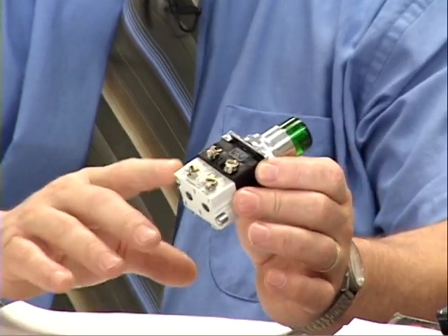And I think, Dan, you were saying that these switches might have normally closed contact symbols shown on them. What were you saying about that? Yeah, that was the point I wanted to make, that the truth table will tell you which contact it is, but don't get confused with normally open or normally closed. That's shown on the physical device, because that might just be the contact block that they had to use to get you to that position. So they use a contact block that's already pre-assembled, that's a normally closed contact. But when they put it under a selector switch, depending upon how the switch setting is used, that normally closed contact under that setting might be open. That's exactly right. Or it might be closed.